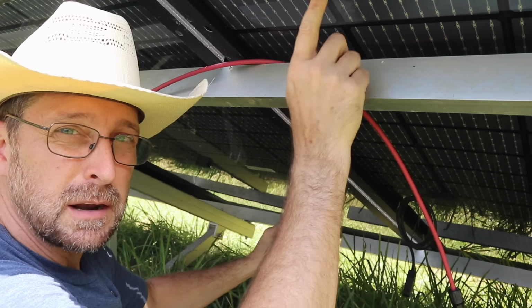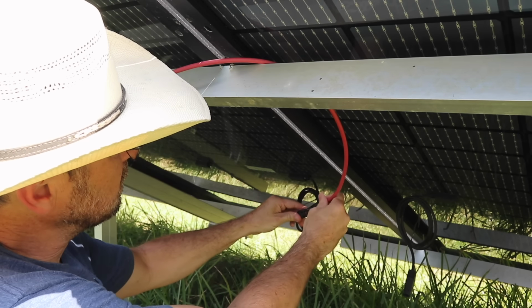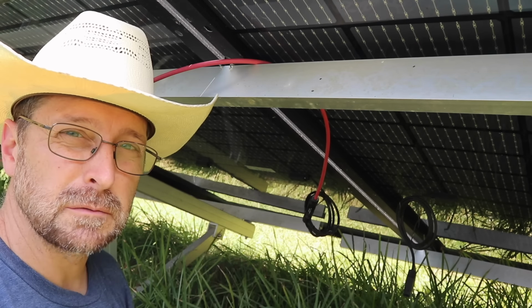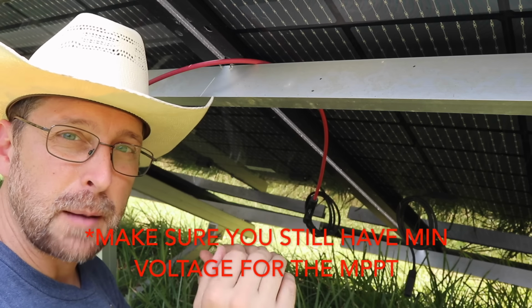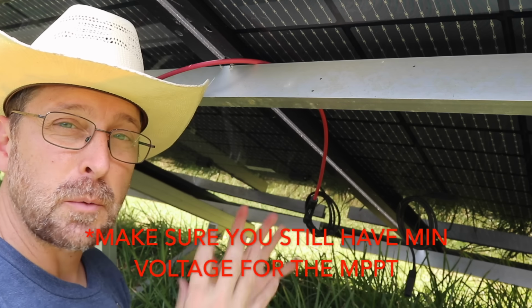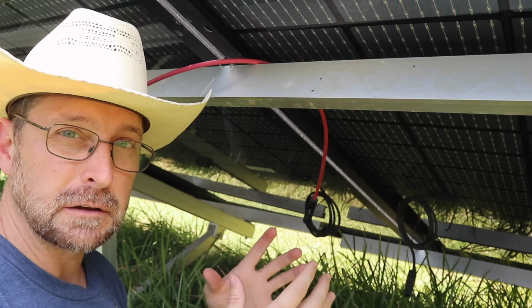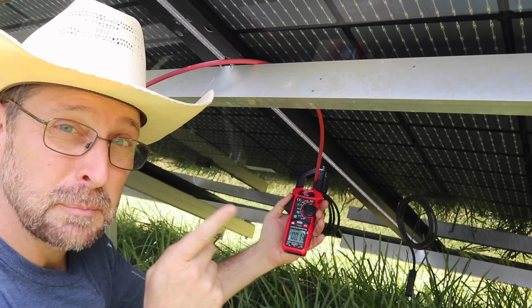And as an aside, bypass diodes can cause hot spots in the panels and at the diodes themselves. So again, a thermal camera is going to be a very valuable tool for you. Okay, I've disconnected this panel right here, and I'm going to reconnect to the panel next to it. Now the voltage on the full string is going to drop, obviously. I took a panel out, but I want to see if the current is still fluctuating. I didn't get that lucky. It's not this end panel.